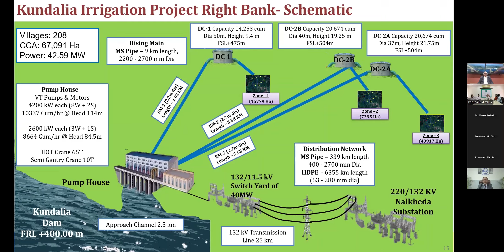Then there was a power requirement. So we have a 132 by 11.5 kV switchyard, with installed capacity of 40 megawatt on the right bank and 30 megawatt on the left bank scheme. We are tapping 132 kV from a 220 kV substation, and power reaches the headworks, from where VT pumps lift the water. So this is a typical scheme and how it works.